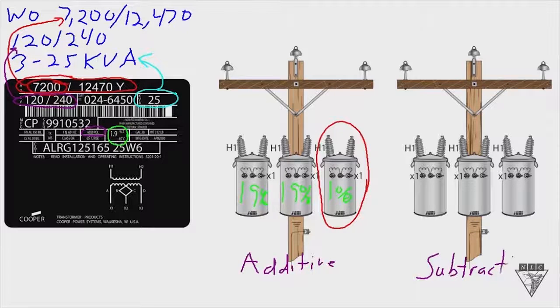electrically you can connect it and make it work. But it's going to be a different type of connection than the traditional connection. And this can be a hazard, especially in the middle of the night. If you come up on a connection, you're like, what is this? I've never seen this before. It could actually be a safety concern. So although electrically it will work, you want to try and find 3 transformers that have the same polarity, just to make it so the connections are traditional and look the same.